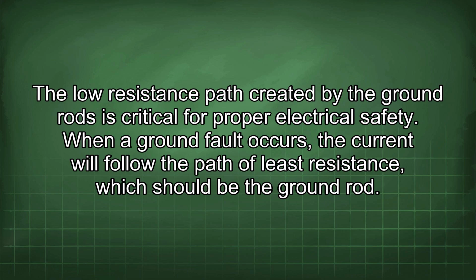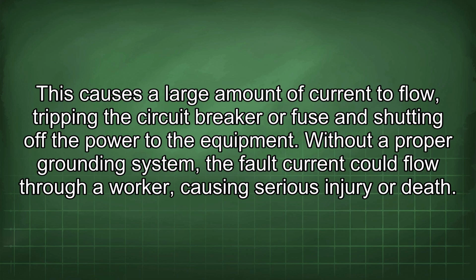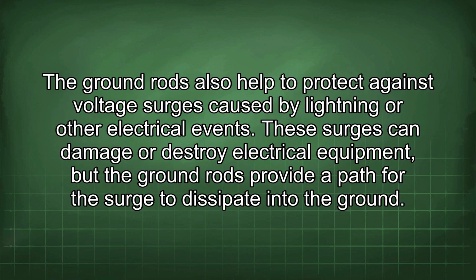When a ground fault occurs, the current will follow the path of least resistance, which should be the ground rod. This causes a large amount of current to flow, tripping the circuit breaker or fuse and shutting off the power to the equipment. Without a proper grounding system, the fault current could flow through a worker, causing serious injury or death. The ground rods also help to protect against voltage surges caused by lightning or other electrical events. These surges can damage or destroy electrical equipment, but the ground rods provide a path for the surge to dissipate into the ground.